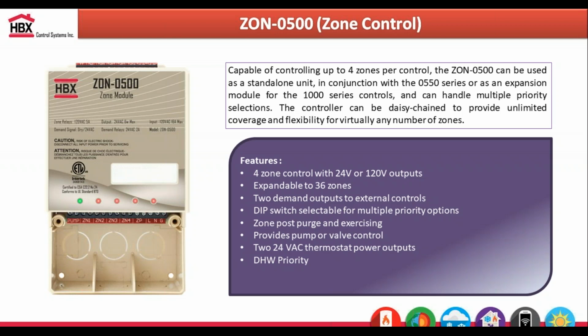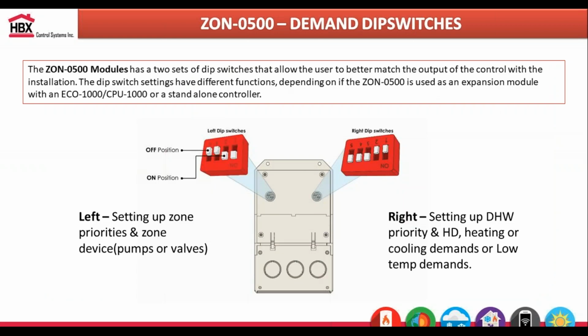For guys that are just wanting your normal everyday zone controller, we have our Zone 500, kind of the same logic as our Zone 550. You can do 4 zones, pumps or valves. There's no forced air elements on there, but you can use anyone's thermostat. So it doesn't have to be an HBX thermostat. You can use whatever thermostats are in the market, commonly 2, 3 or 4 wire thermostats, to the Zone 500. Again, 2 demand outputs to external controllers for your boiler, for your heat pumps. There's 2 sets of dip switches on the back, so you can set your priorities and tell the controller if you're using pumps or valves. So this is kind of your everyday zone controller.